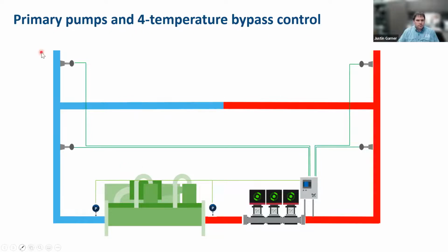But as we go and talk about operation, and we talk about the primary pump set and that 4 temperature bypass control you see here, here's a very exploded view to give you an idea of what I'm talking about. So we have our primary pump set over here. Of course, we have our chiller. The first thing I want to point out is that we have a pressure differential sensor across the chiller. This is how we're going to establish the first priority for the pump controller. The first thing we want to do is make sure the minimum flow requirement for this particular chiller is satisfied. All right, and we won't do anything until that is satisfied.